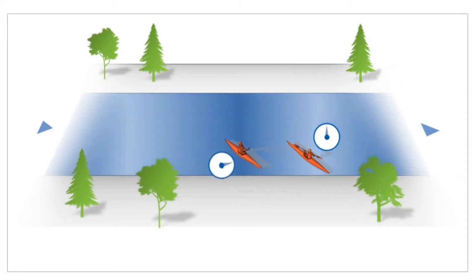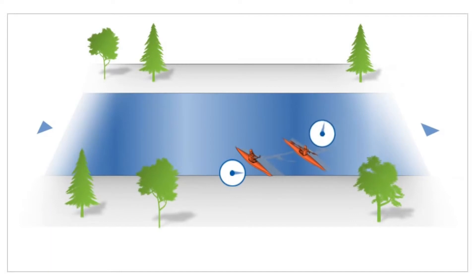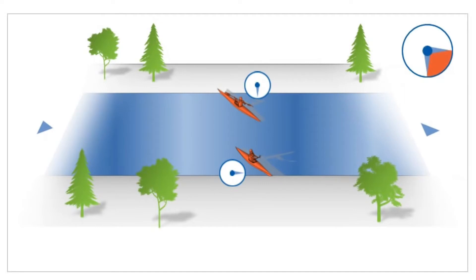Ultrasonic flow measurement with the transit time difference is based on one simple physical fact. Imagine two canoes crossing a river diagonally on the same line — one in the direction of the flow and the other against it. The canoe moving in the direction of the flow needs considerably less time to reach the other riverbank than the canoe moving against the direction of the flow.